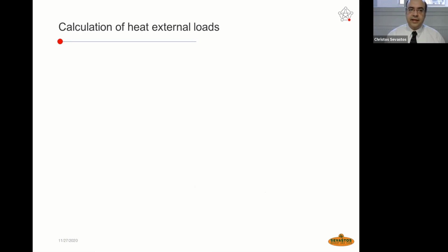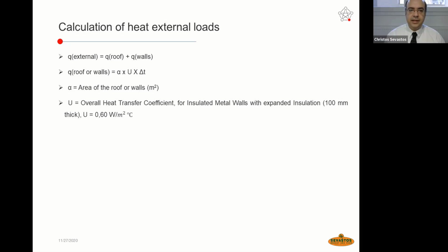Now, the other factor in the equation, in order for us to define the overall heat which is going to be needed for calculating the air ventilation rate, is how we're going to calculate the external heat loads. The external heat loads come from the transmitted heat from the roof and the walls. This heat is calculated from the area of the roof and the walls, the overall heat transfer coefficient for insulated metal walls with expanded insulation of 100 millimeter thickness, which is 0.6 watt per square meter per 1 degree Celsius, and of course the gradient of temperature, which is the difference between the temperature of the walls and roof and the indoor temperature.